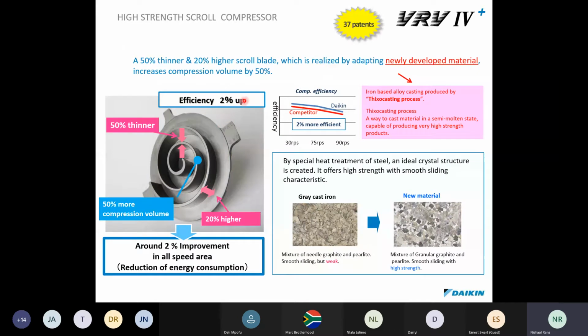So how have we increased this efficiency? We've gone 50% thinner on the compressor blade, the scroll blade, sorry, and that is realized by adopting new material. The new material is a Thixocasting process, which is an iron-based alloy, and it's a way to cast a material in a semi-molten state capable of producing very high strength products. So what that means is that you can go thinner on the material, but you're not compromising on the strength and the quality. But by going thinner, you're also achieving a higher efficiency, and that's what we've done. So overall, we've come up with a 2% more efficient compressor.